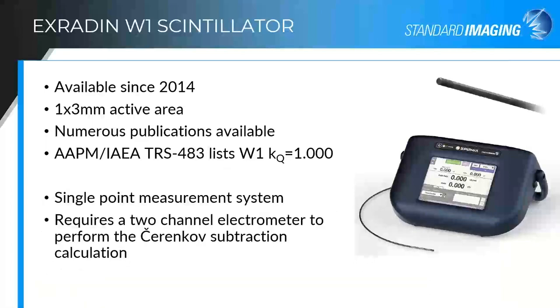The W1 is still a single point measurement system. It was not necessarily designed for water tank scanning, although it is watertight and can be used in a water tank. It does require a two-channel electrometer in order to perform the Cherenkov subtraction calculation.